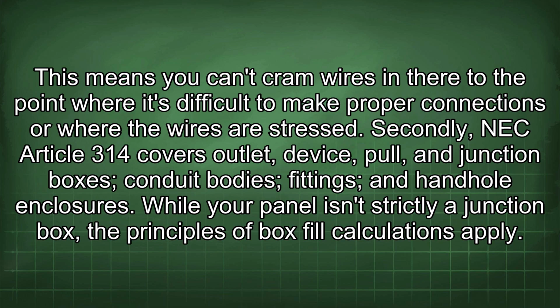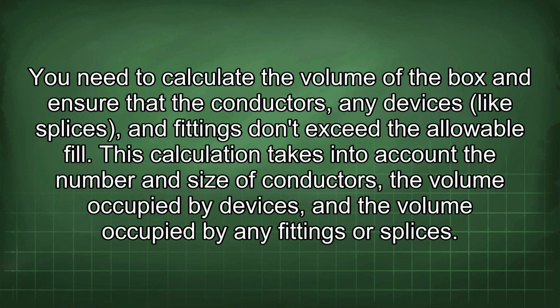Secondly, NEC Article 314 covers outlet, device, pull, and junction boxes, conduit bodies, fittings, and handhole enclosures. While your panel isn't strictly a junction box, the principles of box fill calculations apply. You need to calculate the volume of the box and ensure that the conductors, any devices like splices, and fittings don't exceed the allowable fill. This calculation takes into account the number and size of conductors, the volume occupied by devices, and the volume occupied by any fittings or splices.